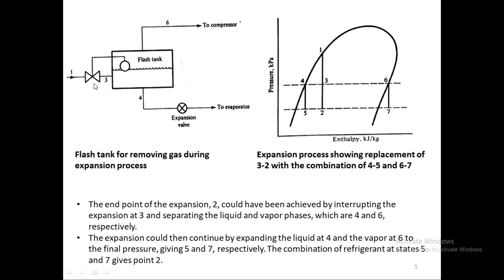The refrigerant comes in at state 3 where we install the flash tank. Gas or vapor goes to the compressor at state 6, and the liquid goes through the expansion valve to the evaporator. The flash tank performs as the flash gas removal system. Vapor velocity inside the tank should be less than 1 meter per second to provide adequate separation, determined by dividing the volumetric flow of vapor by the liquid surface area. The most efficient way to remove flash gas would be to separate it continuously as it forms, but no practical means has been developed for that.